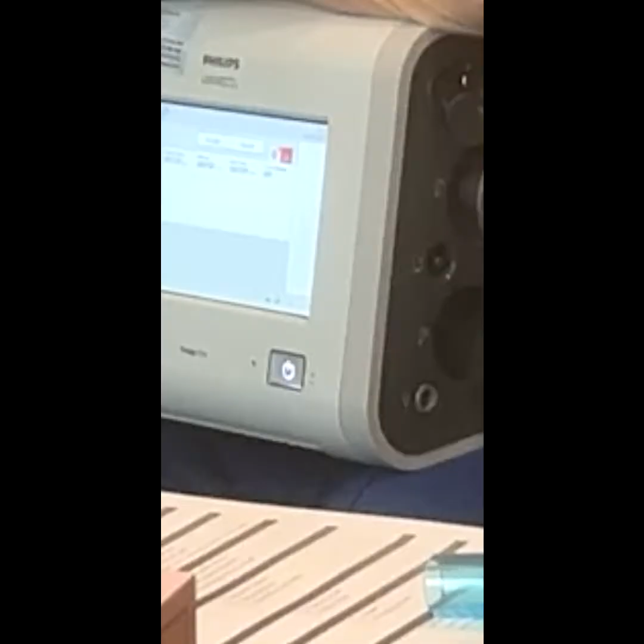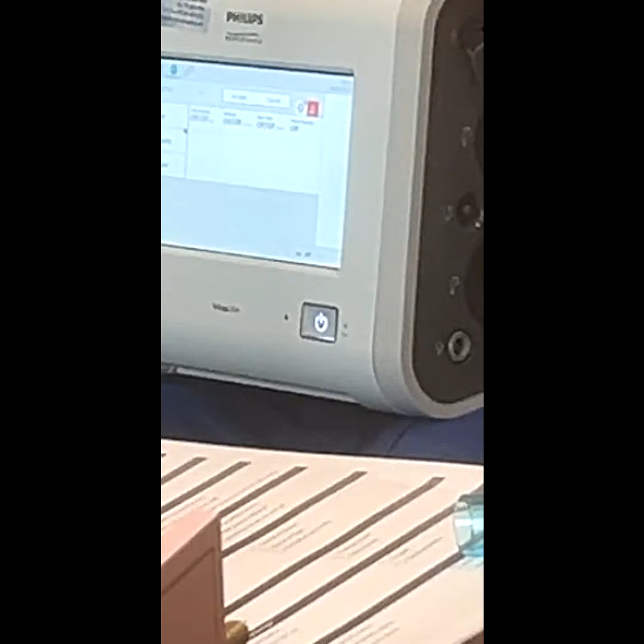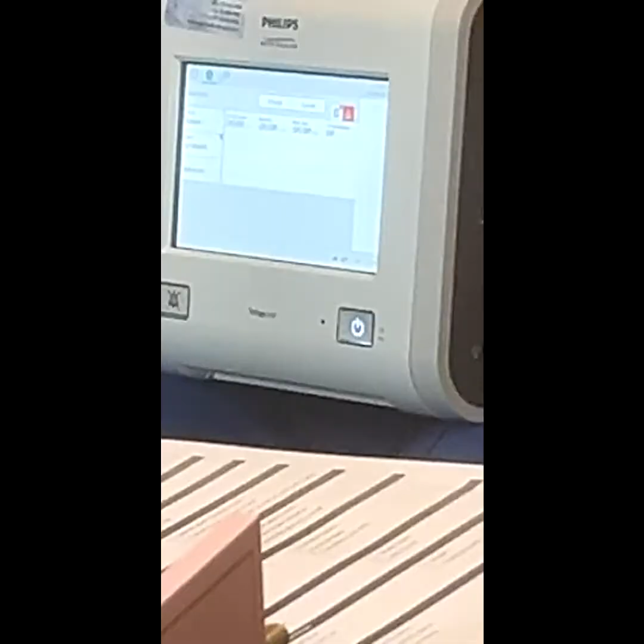Breathing treatment, whatever, suction, whatever, saline, whatever, okay? You may get one that's saying the patient's over breathing or whatever, and a lot of times it's probably because of a mucus plug again, okay? Whereas on the Trilogies, you had a check circuit or a low circuit leak. Check circuit was this too, yeah. Low circuit leak was because the exhalation valve wasn't on, okay? Or it was turned upside down, or it was coated with secretions, okay?